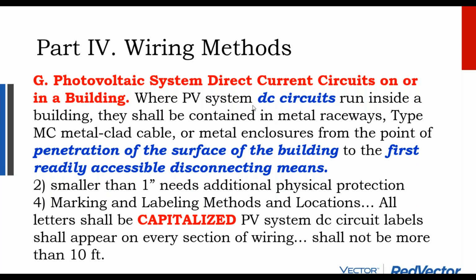So solar circuits have this requirement that inside the building, DC circuits, not AC circuits, but DC circuits have to be in metal. That metal is there for physical protection. So is there a real reason why AC versus DC, why AC gets the exemption? Well, no, it's really nothing more than DC discrimination. If AC had to be in metal, that would raise all sorts of questions about utility service entrance cables going inside the building with plastic protection rather than metal protection. Also heavy high amperage AC load circuits, they're run in Romex, and so if solar AC circuits like from microinverters needed this metal protection, it would open up a can of worms that I don't think the industry needs to consider.